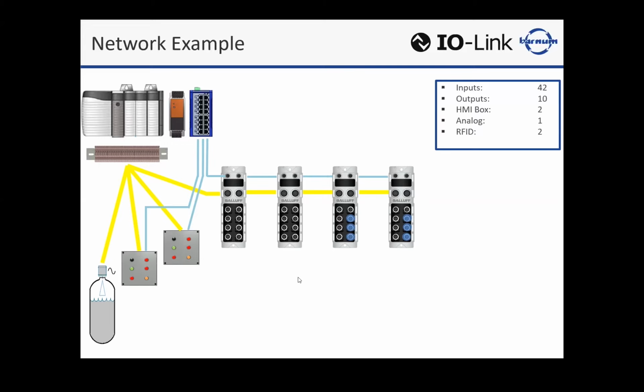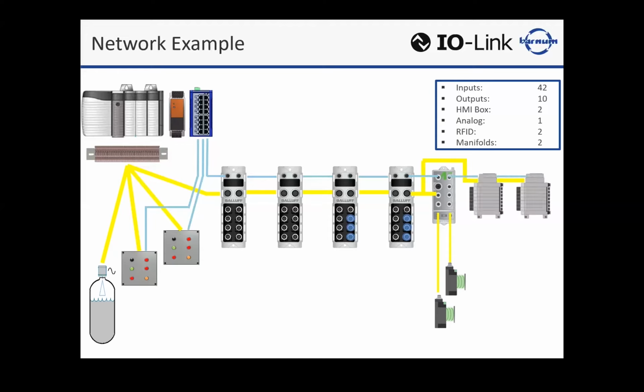We have the RFID in this case. Yep. Still going to need a processor, because the RFID data is taken on a subnetwork, essentially taken to that processor. That processor converts it to data that can be read at the Ethernet IP protocol or Profinet protocol. So yeah, still need a processor and two heads. And then our two manifolds go out there and they use a valve manifold communication module for Ethernet IP.